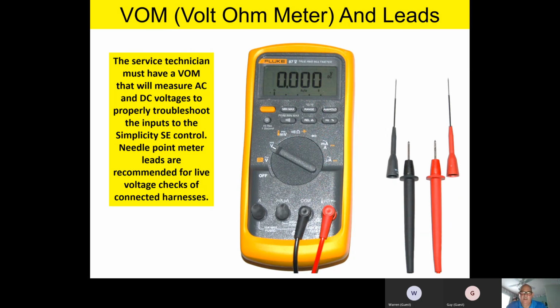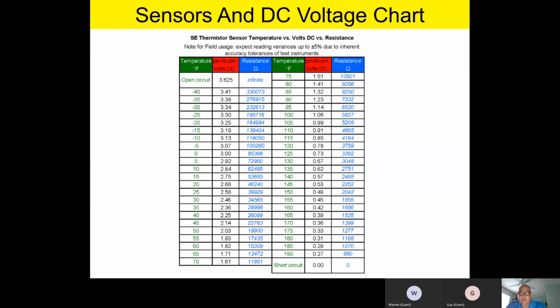Now on those sensors, you're going to notice there's a sensor chart, which you'll typically find in your install information with the equipment. That sensor chart is set up to show a temperature, a resistance, and a voltage at any given temperature. To give an example, if I'm looking at this sensor chart and I want to know the pin-to-pin voltage with the sensor plugged in and my needlepoint meter leads, let's say at 0 degrees Fahrenheit, as you can see on our screen, reading the DC voltage on that sensor plugged in, it should be 3 volts DC.